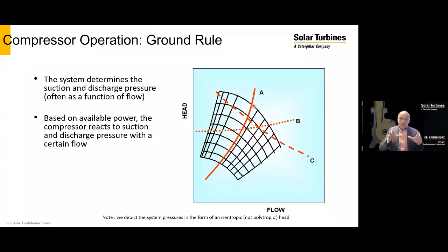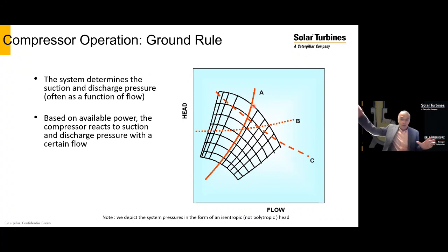And this is actually a very powerful concept. I was at a compressor station last week where we essentially used these concepts to operate the machines that we wanted to test at specific operating conditions, simply by manipulating the conditions that the system around the compressor imposed on it.